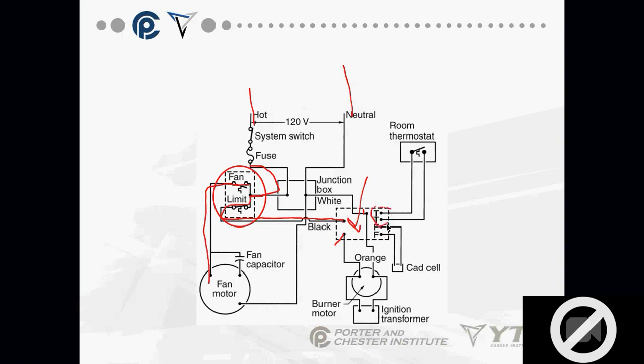There's the TT terminals that I said. This is R and W on the thermostat. So when my thermostat calls for heat, I close R to W, and effectively I'm putting a wire across T and T. Okay, and that starts my whole heating cycle.